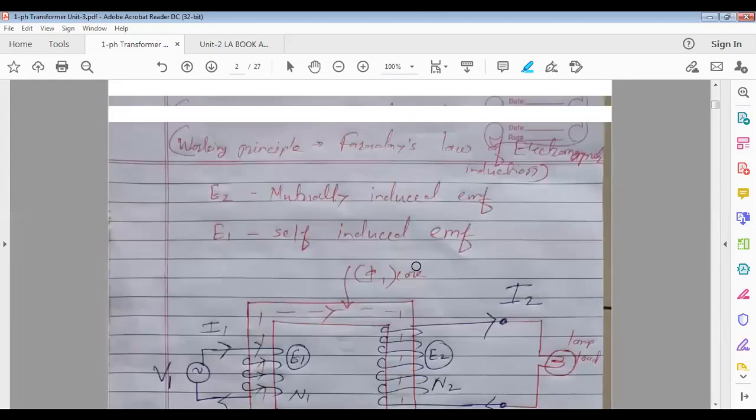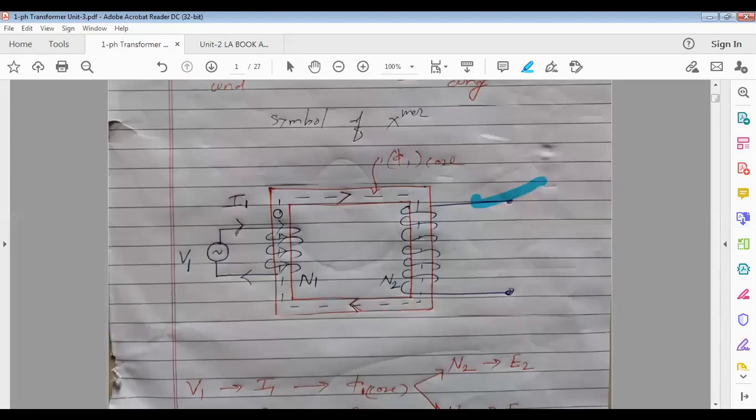See now, this is the core. If you observe this core, it has a vertical side limb, isn't it? So what is done? Vertical plates of this dimension and thickness 0.3 mm to 0.5 mm get manufactured. Because this vertical plate is required on your left also and on your right also, isn't it?